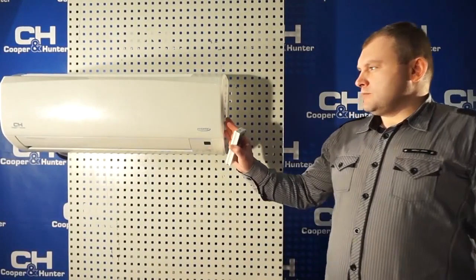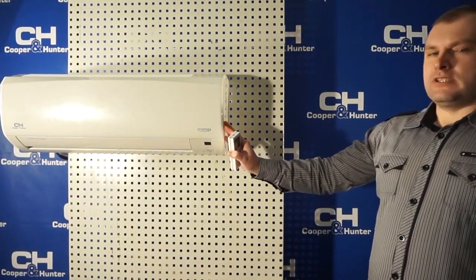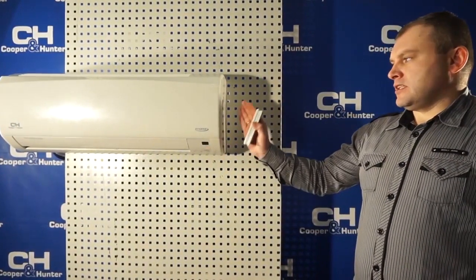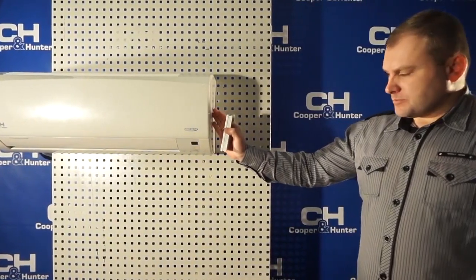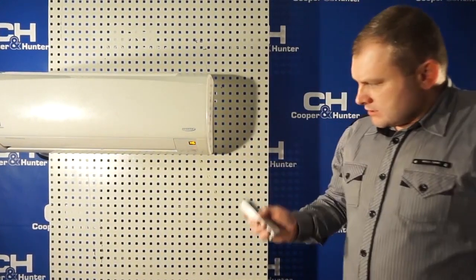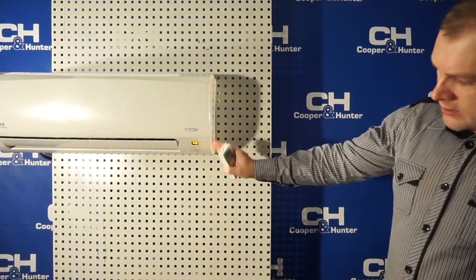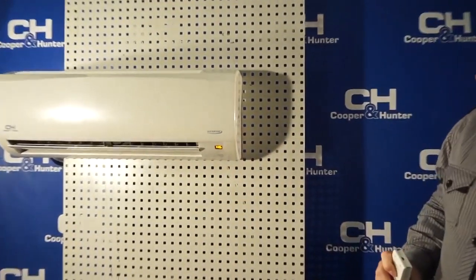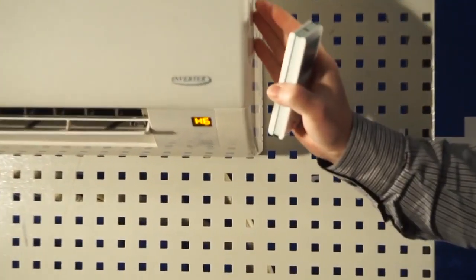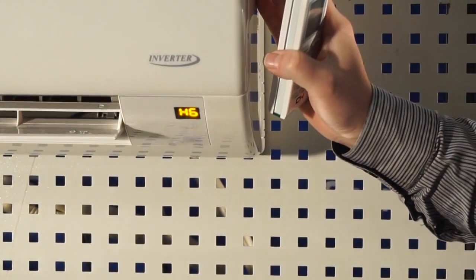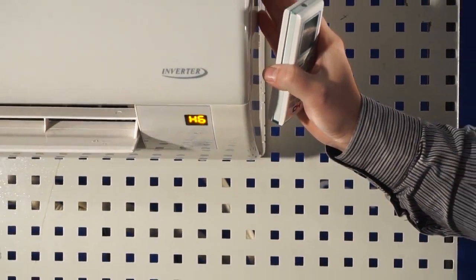For diagnostics, we will use the favorite model of residential air conditioner Cooper&Hunter CHS09FTXN. Proceed to diagnosis. When displaying error H6, this means that the main board does not receive information on the speed of the fan motor of the indoor unit.